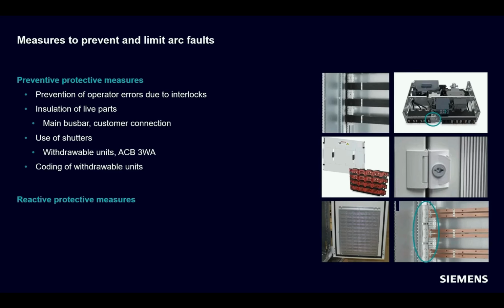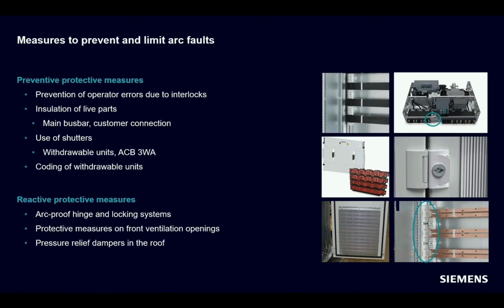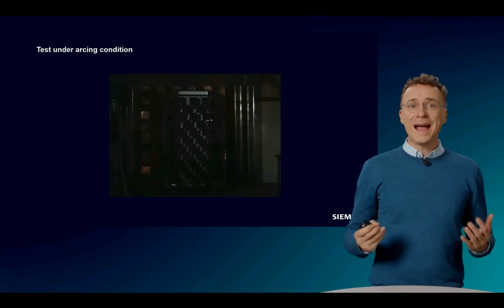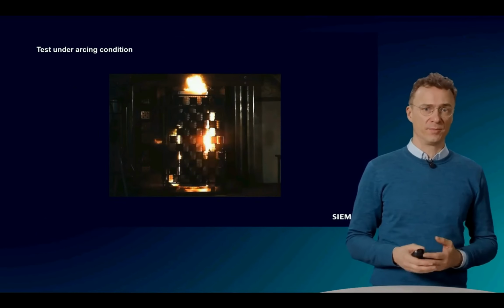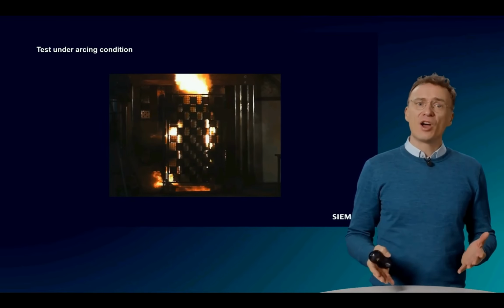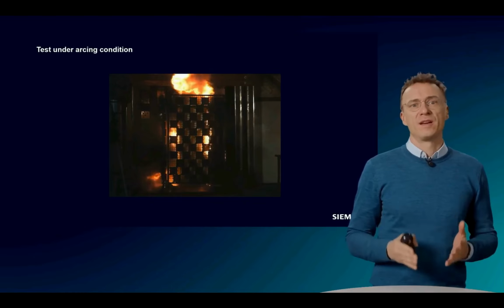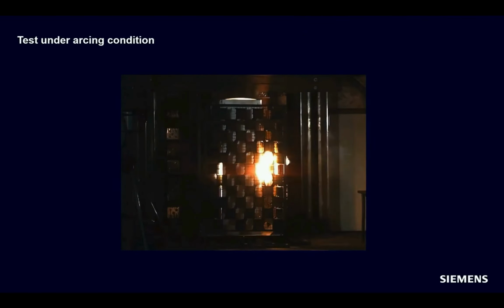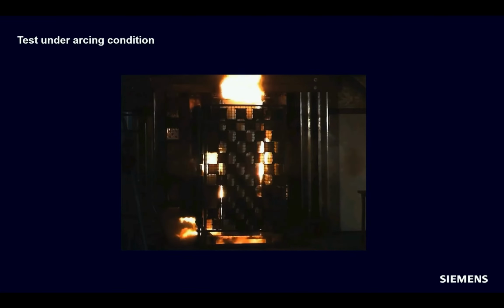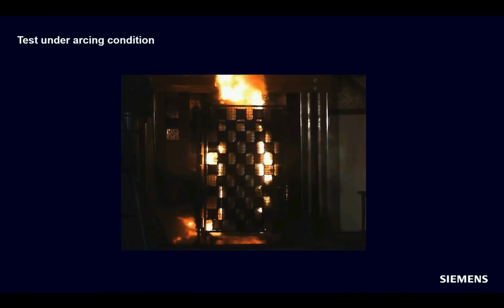Reactive measures include, for example, the arc-resistant hinge and locking system, as well as protective measures at the front ventilation openings, along with pressure relief flaps in roof plates. Furthermore, the use of the arc barrier, which prevents the arc from moving from one cubicle to the next, is a simple and efficient means of limiting an arc fault to one cubicle. But is that all enough? As always, it depends on what is to be achieved. However, the requirements of IEC Technical Report 61641 can be met in any case. This still looks spectacular in the high-speed recording, but this is a past test with the classic upgrade measures.